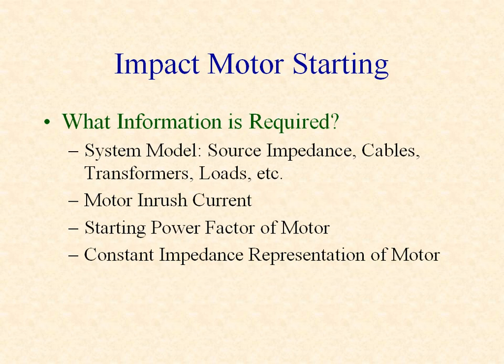Impact motor starting needs essentially the same information that's required to perform a load flow simulation. You need to build a system model that includes the source impedance, cables, transformers, and loads. You need to know the motor rated size, inrush current, and starting power factor. The motor starting condition is automatically represented by a constant impedance load.